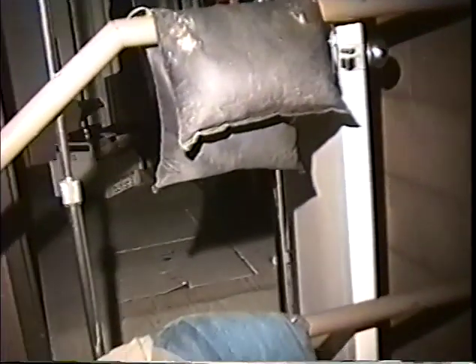And if you look directly behind us here, you'll see another door leading to a storage room behind the stage, which is propped open by a microphone stand. Once again, this is the type of door that should be normally closed at all times. It does have a pneumatic closure, and it's a rated device.